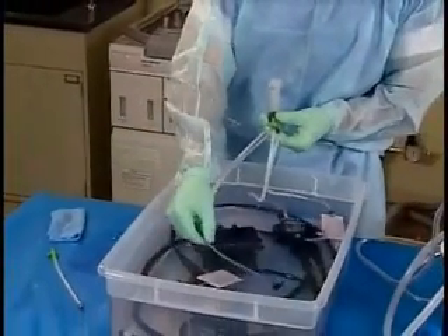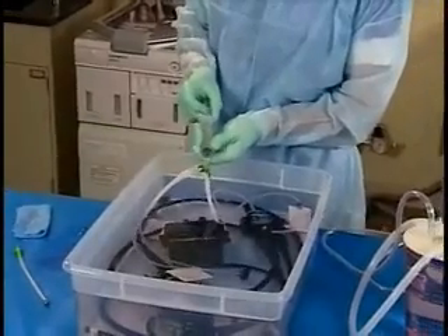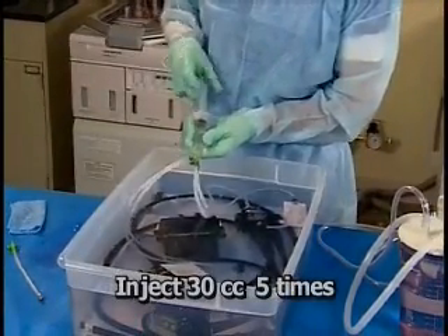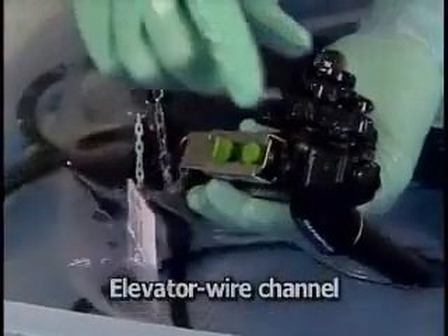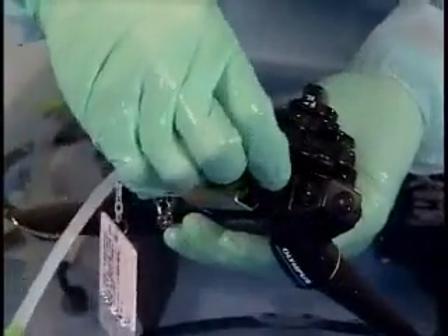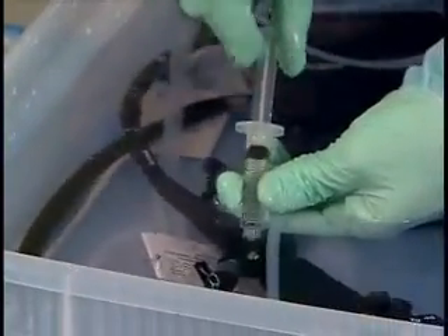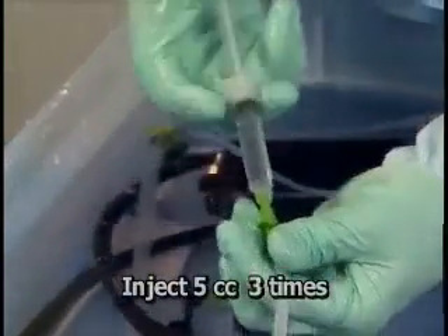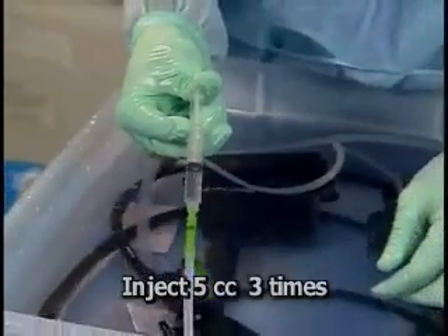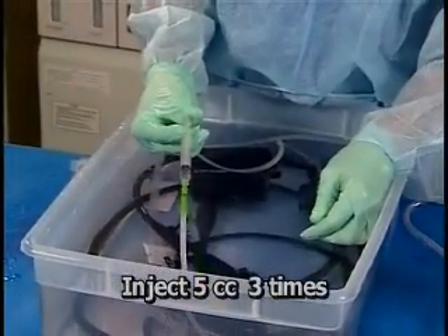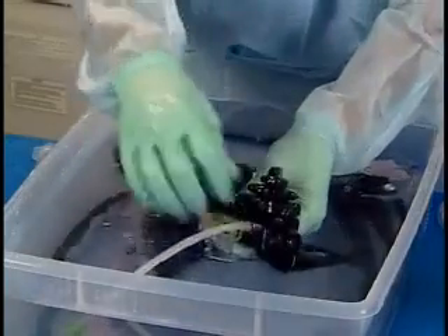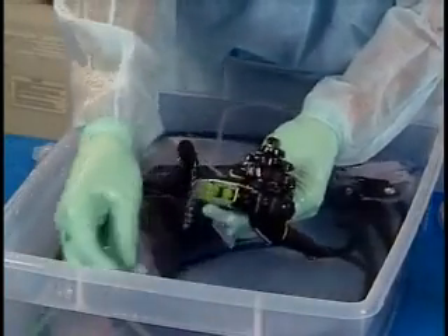With the intake filter immersed in detergent, use the syringe to flush 150 cc's of detergent solution through the air, water, and balloon channels. If you are reprocessing an endoscope with an elevator, attach the washing tube to the elevator plug. Use a 5 cc syringe and inject 15 cc's of detergent into the elevator wire channel. Disconnect the washing tube and all other cleaning accessories from the endoscope and immerse them in detergent solution.